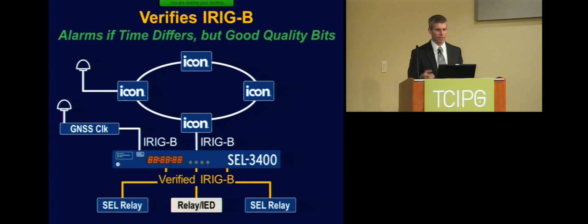So this device comes in, measures the rising edge at start of second, and if the time quality for both signals says it's good, but the device sees one edge is 400 microseconds off from the other, that tells you either you have an equipment problem or one of your antennas is being spoofed.